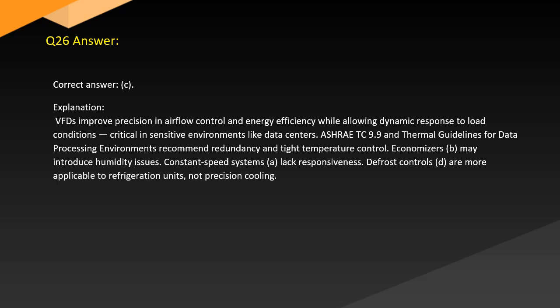Answer. Correct answer: C. Explanation. VFDs improve precision in airflow control and energy efficiency while allowing dynamic response to load conditions. Critical in sensitive environments like data centers. ASHRAE TC 9.9 and thermal guidelines for data processing environments recommend redundancy and tight temperature control. Economizers (B) may introduce humidity issues. Constant speed systems (A) lack responsiveness. Defrost controls (D) are more applicable to refrigeration units, not precision cooling.